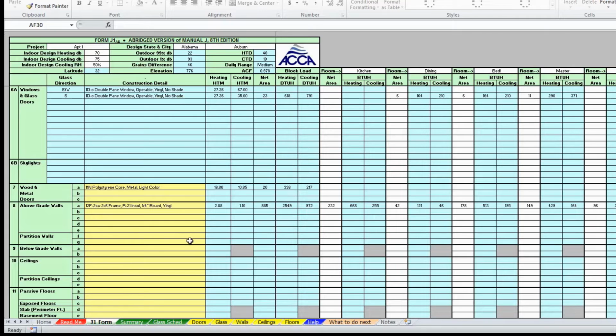Let's go down. We've got below grade walls. We're going to do the same thing. We're going to take the perimeter of the whole building and basically input every piece that we did here. We're just going to go ahead and copy that all down. Then the ceilings. Now we're taking the area of each room, and we're going to have to divide this a little bit differently. If you had a room that was just flat ceiling, or a house that was flat ceiling the whole way across, it's easy. You just take the area of every room, put it in there, and you're done.